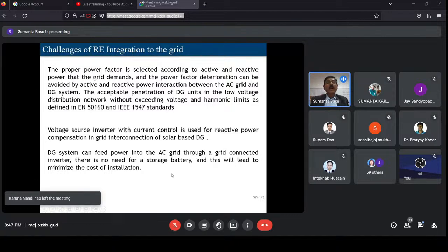Another big challenge to the RE integration to the grid is the active and reactive power component that the grid demands. For the distributed generating units, which comprise various types, the low voltage distribution network has to limit the harmonics and not exceed the voltage regulation criteria as defined in the EN 50160 and IEEE 1547 standards. So whether we design the inverter or the power system network or microgrid, these aspects need to be taken care of.